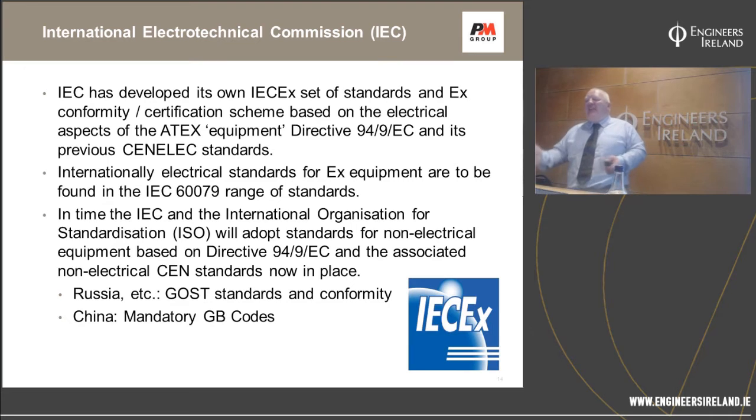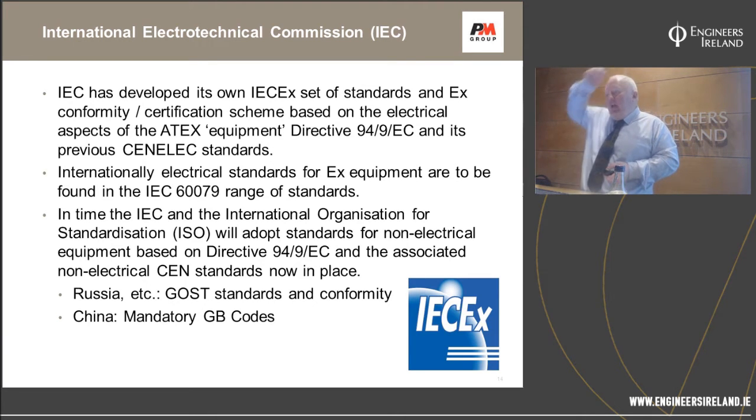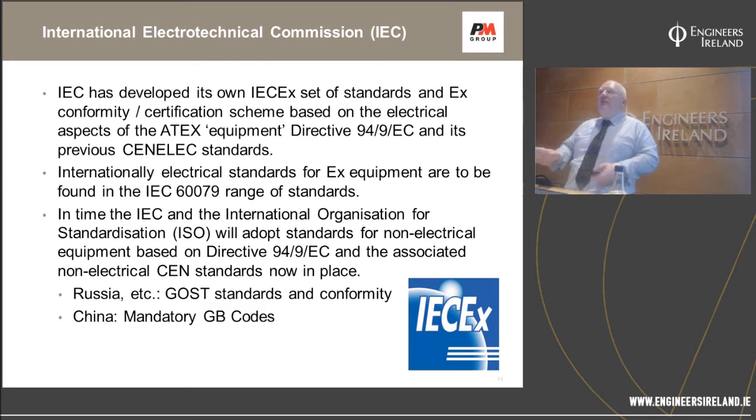Anyhow, internationally, the International Electrotechnical Commission has developed its own IECEx set of standards and its conformity certification scheme. Basically, they took all the good electrically oriented material that came out of Europe from 94/9 and all the harmonized standards, and put them into the IEC 60079 range of standards. So nearly everything you need to know for ATEX electrical is in this IEC 60079 range, and you can use that globally. If you're an expert in that in Ireland, you can be an expert in that in Singapore, and even now in the United States, or Russia, or wherever you want to be. And in time, the IEC and the International Organization for Standardization, the ISO, are adopting the non-electrical standards that the Europeans developed.